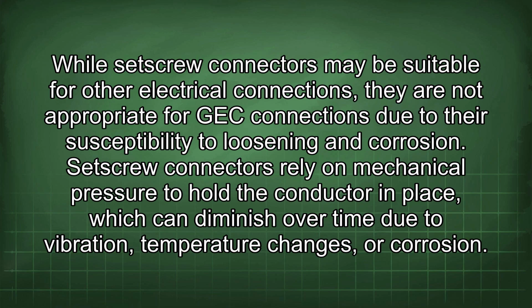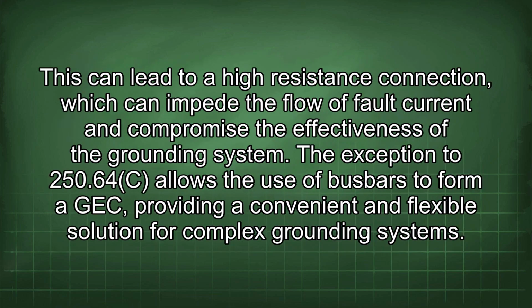Set screw connectors rely on mechanical pressure to hold the conductor in place, which can diminish over time due to vibration, temperature changes, or corrosion. This can lead to a high-resistance connection, which can impede the flow of fault current and compromise the effectiveness of the grounding system.